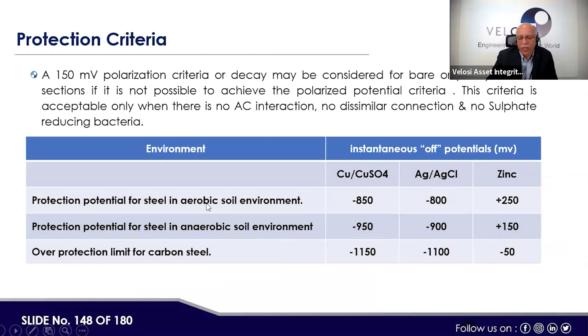Here protection criteria also matter, like whether minus 850 millivolt or minus 950 millivolt for the protection potential for steel in anaerobic soil environment, then over protection limit for carbon steel minus 1150 for copper sulfate or AgCl or zinc environment. So it's important to see if we are within the acceptable range of protection or potential difference.